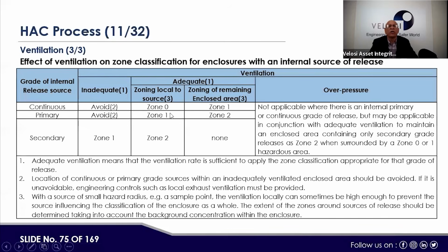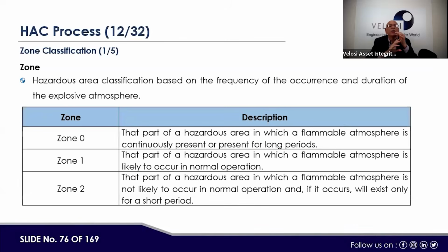So here we need to establish the ventilation as per the applicable level of that zoning. For example, if we don't want the presence of those hydrocarbons for a longer period, then the ventilation system should be a good one. And if we allow a longer period, then the installation of electrical equipment for zone 0 is very costly to maintain. So again, hazardous area classification is based on the frequency of occurrence and the duration of exposure to the atmosphere.